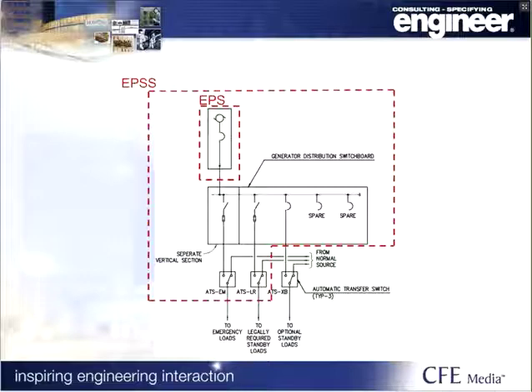Notice I did not include the optional standby transfer switch in the EPSS. The criteria applies to the emergency life safety and standby systems as required by code. There is no requirement to ensure the optional standby systems will operate and perform to the level of the code-required systems. And then here I'm noting the load terminals on the transfer switches.